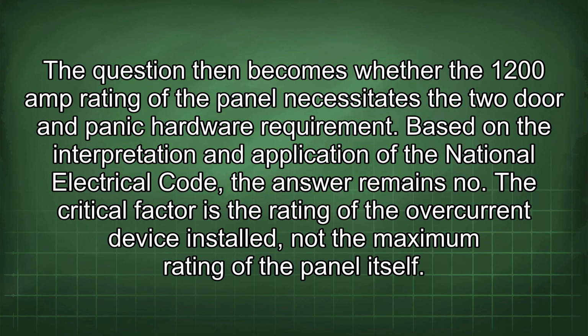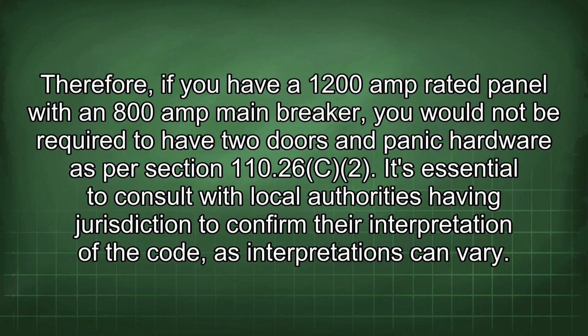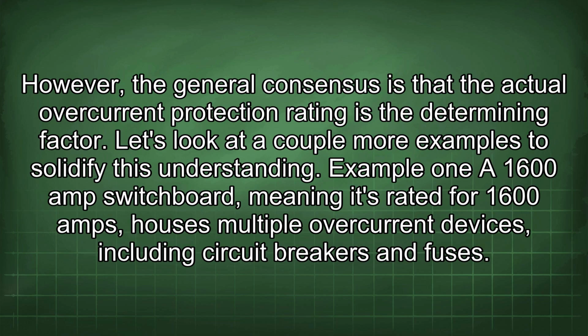The critical factor is the rating of the overcurrent device installed, not the maximum rating of the panel itself. Therefore, if you have a 1200 amp rated panel with an 800 amp main breaker, you would not be required to have two doors and panic hardware as per section 110.26C2. It's essential to consult with local authorities having jurisdiction to confirm their interpretation of the code, as interpretations can vary. However, the general consensus is that the actual overcurrent protection rating is the determining factor.